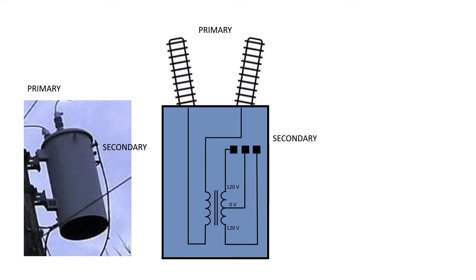Let's take a look at what the inside of a pole transformer looks like in North America so we can see how split phase AC is arranged. The primary connections are usually at the top of the transformer, and the secondary connections are on the side — these are called bushings. The high voltage side could be anything between about 4 kV up to about 20 kV, but the low voltage side in North America is usually fixed at 240V from one side of the transformer to the other.